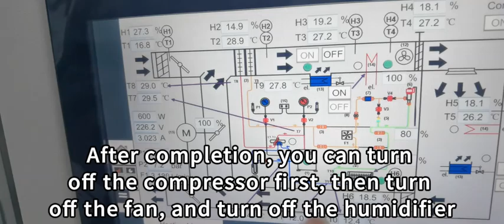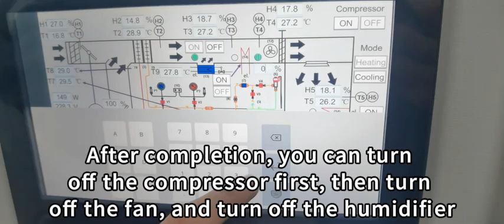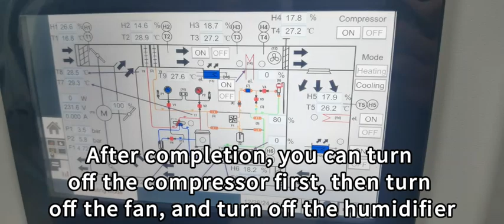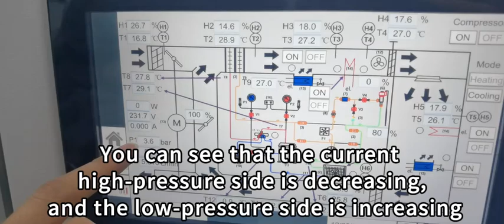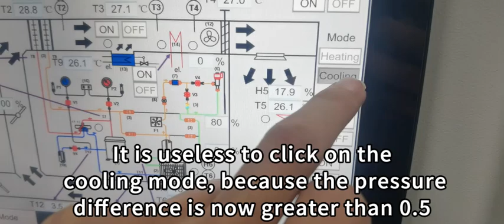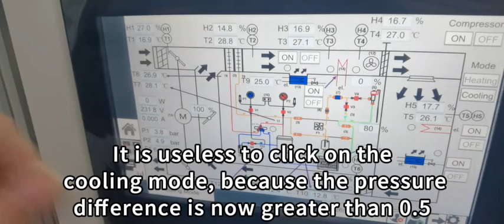After completion, you can turn off the compressor first, then turn off the fan and turn off the humidifier. You can see that the current high pressure side is decreasing and the low pressure side is increasing. Now you can experiment with mode switching. It is useless to click on the cooling mode because the pressure difference is now greater than 0.5.